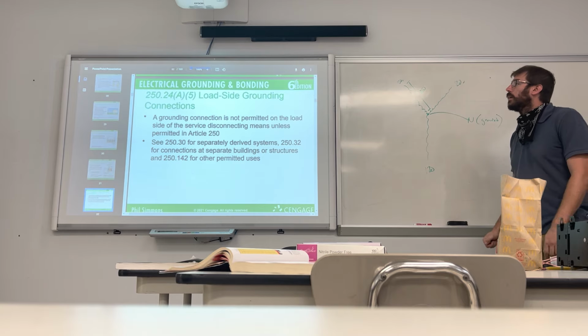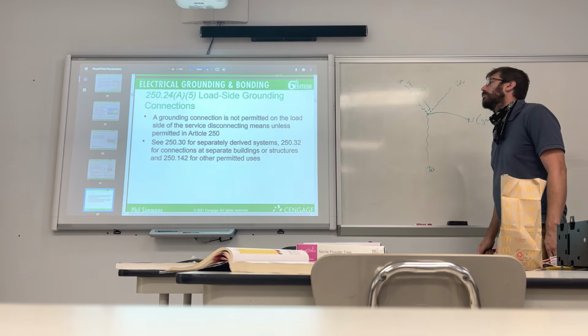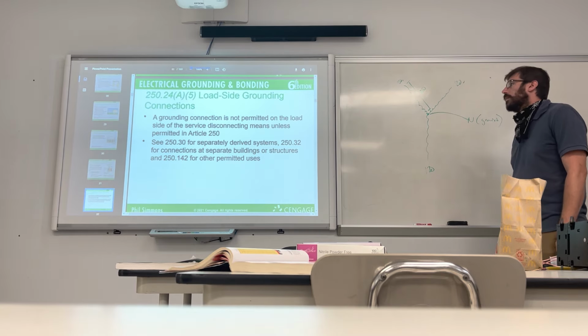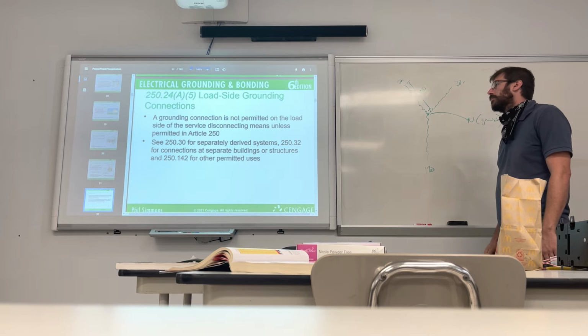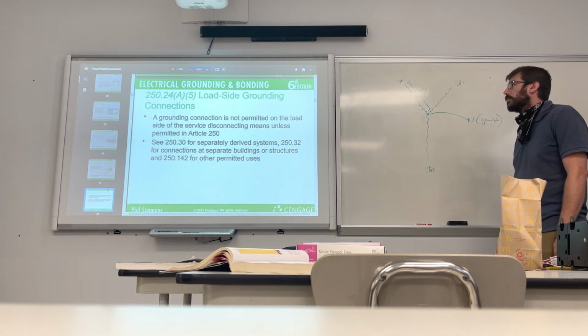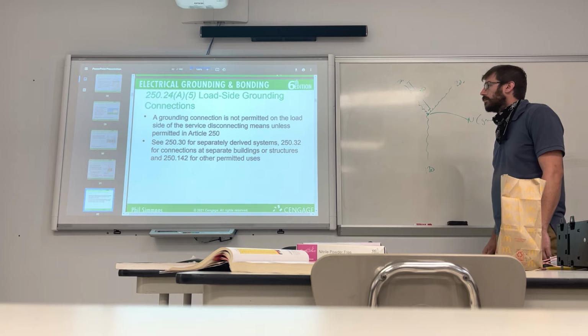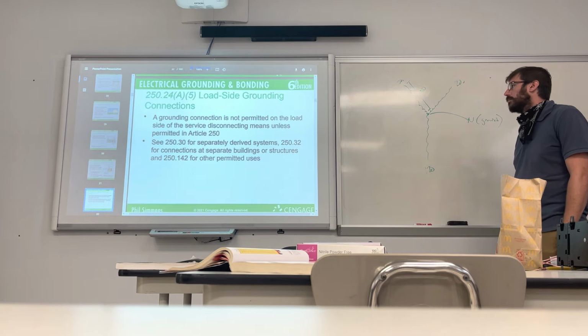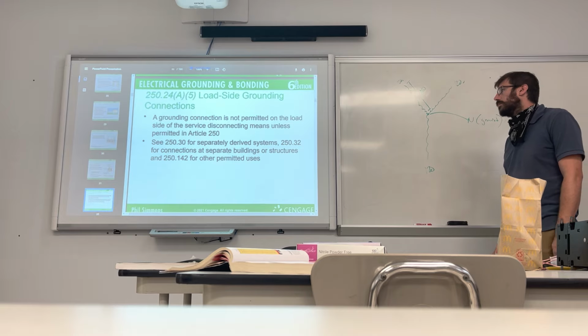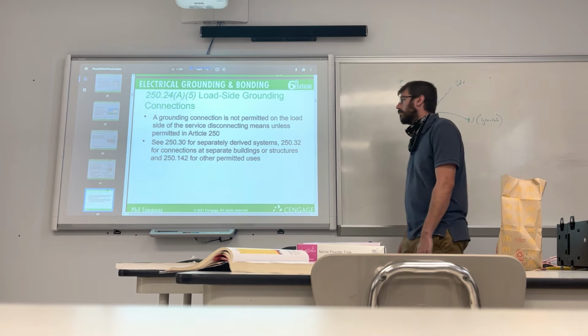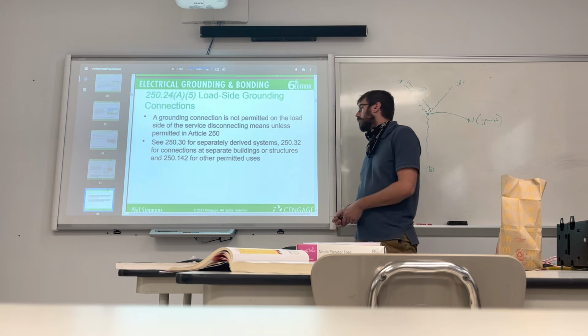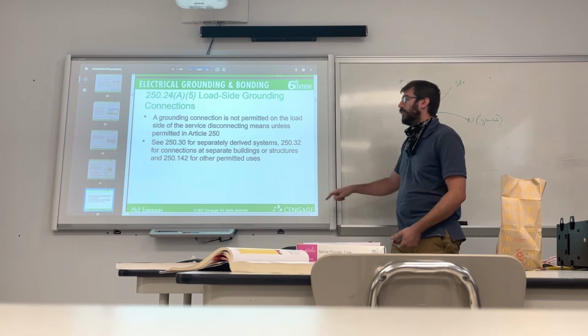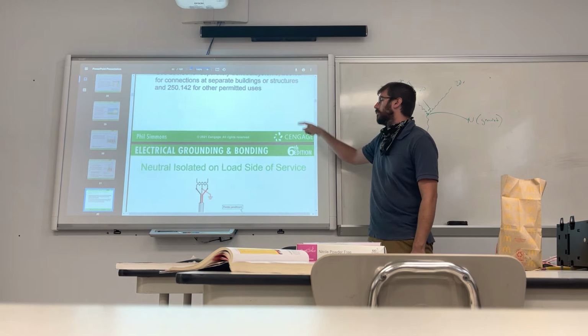Load side grounding connections. A grounding connection is not permitted on the load side of the service disconnecting means unless permitted in Article 250. 250.30 for separately derived systems, 250.32 for connections at separate buildings or structures, and 250.142 for other permitted uses. Yes, 250.142, I know that well. Yes.